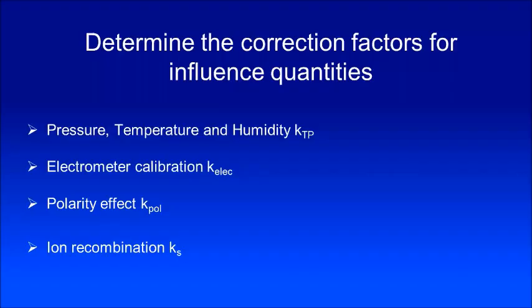The next thing is to determine the correction factors for influence quantities. Number one is the pressure, temperature, and humidity correction factor, called K_TP. Number two is the electrometer calibration factor K_elec, which is required only if your electrometer is calibrated separately from your ion chamber — most often they are calibrated together, so this factor will be one. The third is the polarity correction factor K_pol, and the fourth is the ion recombination correction factor K_s, which must also be determined for your ion chamber.